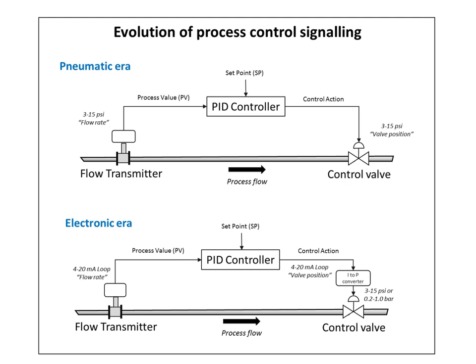Early systems used direct process connections to local control panels for control and indication, which from the early 1930s saw the introduction of pneumatic transmitters and automatic three-term controllers. The ranges of pneumatic transmitters were defined by the need to control valves and actuators in the field. Typically a signal ranged from 3 to 15 psi (20 to 100 kPa or 0.2 to 1.0 kg/cm²) as a standard, with 6 to 30 psi occasionally being used for larger valves.